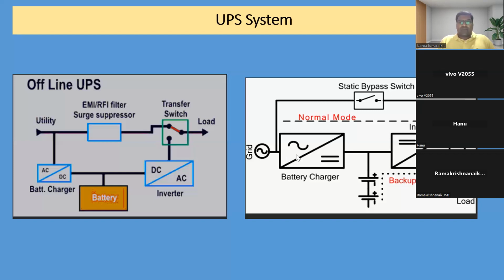You can see static bypass is a standalone or single UPS configuration, from rectifier to battery backup. The battery will get charged and again it will come back to the inverter, then go to the load. In case something happens on the inverter side, some failure, or on the rectifier side something is faulty or any alarm is triggered, it will go to battery mode. The battery will take the load. The battery will have some backup time, probably less than 5 minutes, sometimes based on the load, 10 or 15 minutes, it will give the backup.